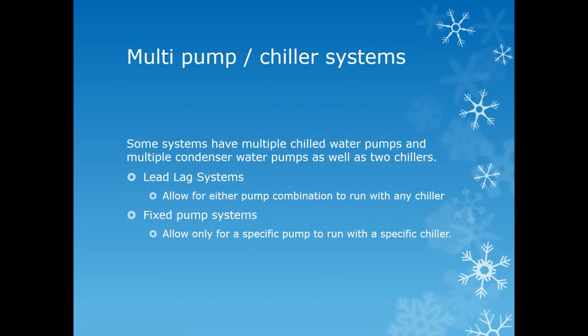Multi-chiller systems are generally designed for system redundancy. These types of systems are generally found in critical areas such as science buildings and medical complexes, where if one part of the system fails another part can be brought online to keep the entire system running. Some systems will have multiple pumps as well as multiple chillers. These systems are often configured in a lead-lag system which allows for either pump combination to be run with any one of the chillers. Fixed pump systems will only allow for a specific pump to be run with a specific chiller.